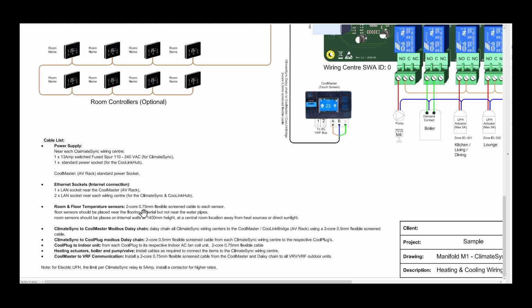Room and floor temperature sensors. So this could be a 2-core 0.75 screened cable, flexible screened cable, or 0.5 flexible screened cable. Floor sensors should be placed near the flooring material, but not near the water pipes. This is to avoid the floor temperature limit being reached when it's not really reached. So sometimes if you put the sensor too close to a hot pipe, way before the floor temperature reaches the floor limit temperature, the pipe already reaches that temperature and will stop the heating for that room. So it's better to install it close to the flooring, just under the flooring, away from the pipes, or away from the heat source if it's an electric underfloor heating.